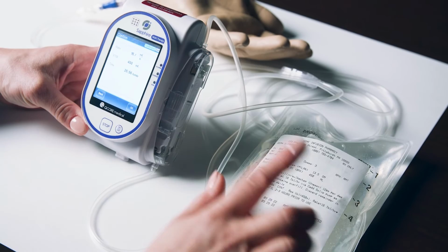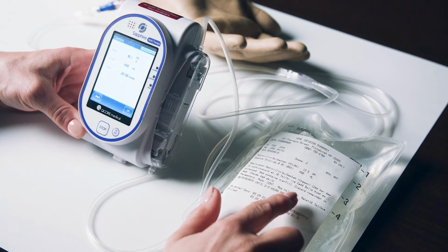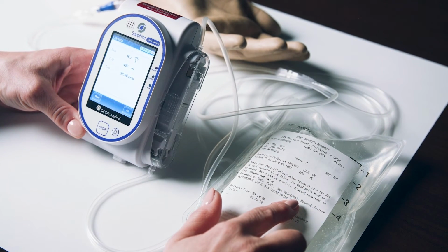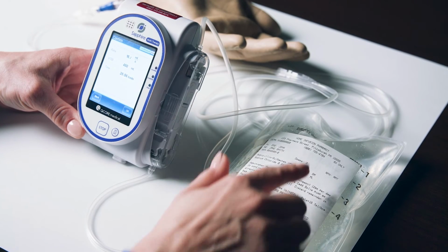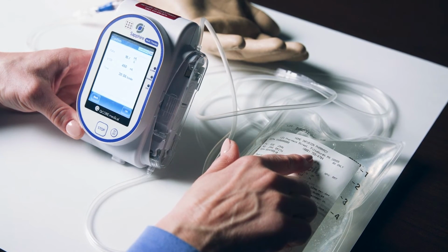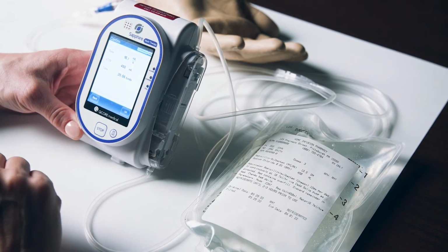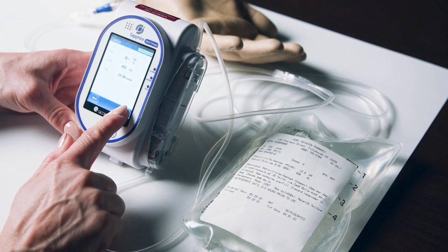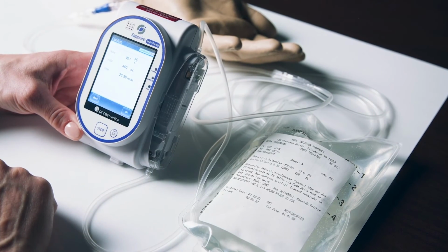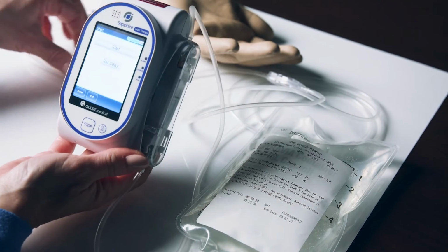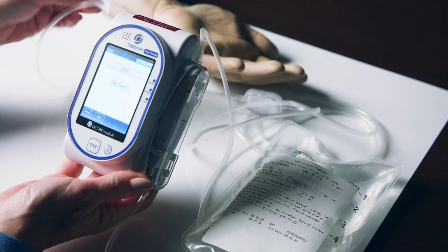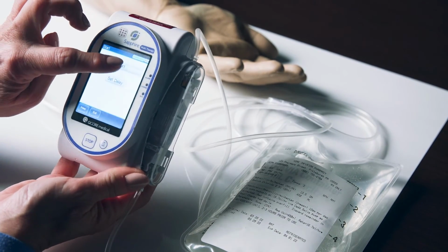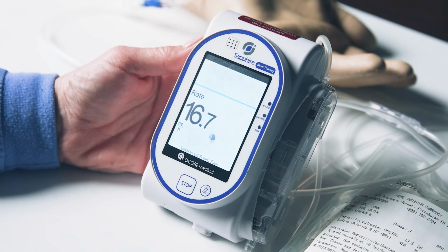When the pump parameters show on the pump screen, compare them to the medication prescription label infusion parameters. Contact your pharmacy if the pump and medication label do not match. Your pharmacy phone number will be on the top of the medication label. If the pump settings are correct, you will press OK. Please double-check that all the clamps on your tubing are open and press Start Infusion.